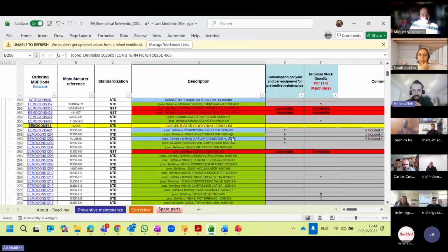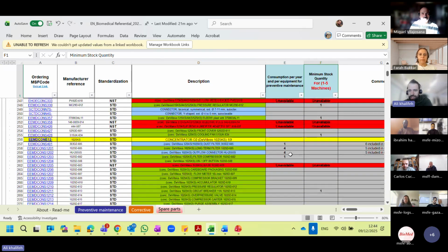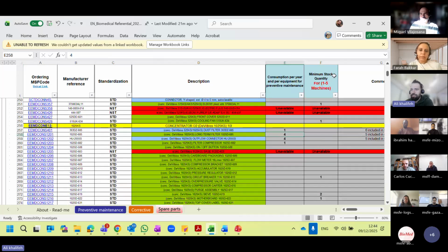So we took all the items, for example the long-term filter. In the recommendation column, we have the recommendation per year per equipment, and the minimum stock per year for 1 to 5 equipment. The idea is that if we have the recommendation per equipment, we need to use that recommendation. For some spare parts, we have the recommendation if we have 1 to 5 units of equipment. For example, for the circuit breaker: if we have 1 concentrator or 5 concentrators, we order only 1 circuit breaker. If we have 6 concentrators, we order 2 circuit breakers. Is the recommendation on this referential clear?